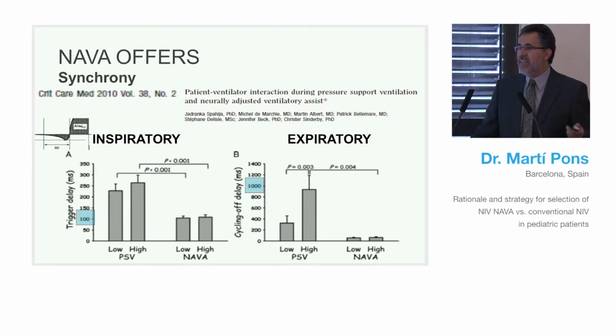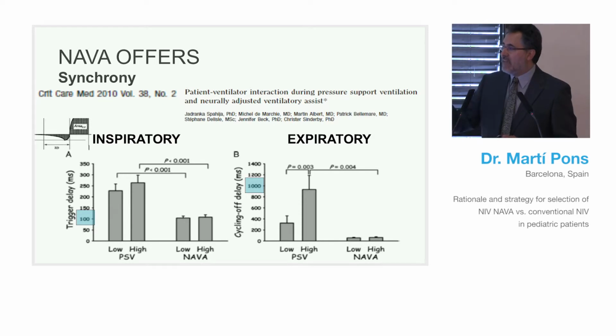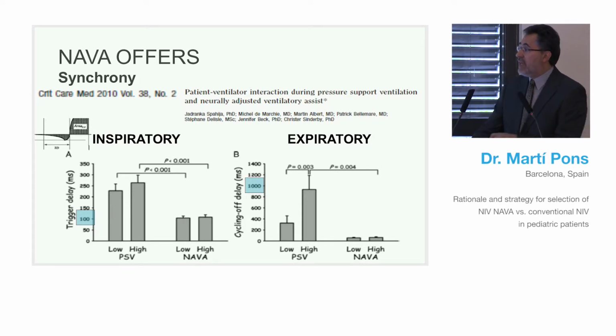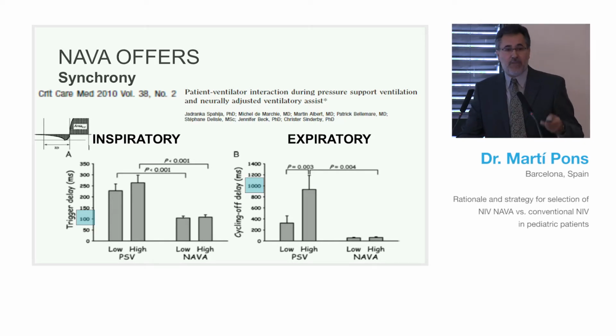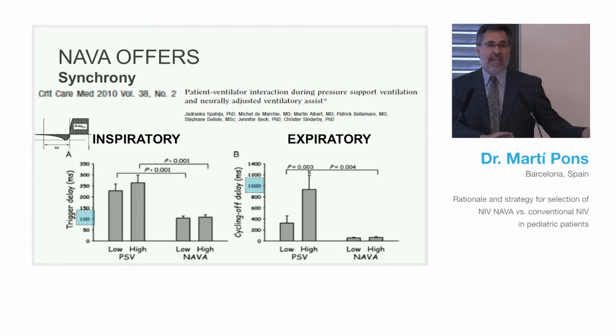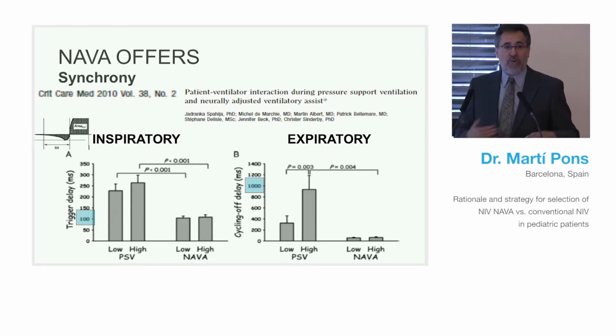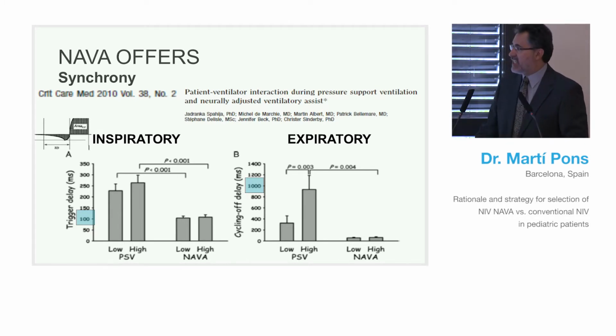Working with BiPAP Vision or other ventilators, they are telling you that really you are lower than 150 milliseconds, and it works pretty well. So really, we are even having shorter inspiratory delay. On the right side, we can see that for the expiratory delay, it can be even worse, especially if the patient needs higher levels of pressure support. The asynchrony can arrive to almost 1 second. That's crazy. When that baby with bronchiolitis has an inspiratory time of 0.3, having an inspiratory time of 1 second is absolutely crazy. So you are going to intubate all these babies, and you say, oh, it's not working at all. So it's not working the pressure support with a nasopharyngeal tube with huge leaks, for example.